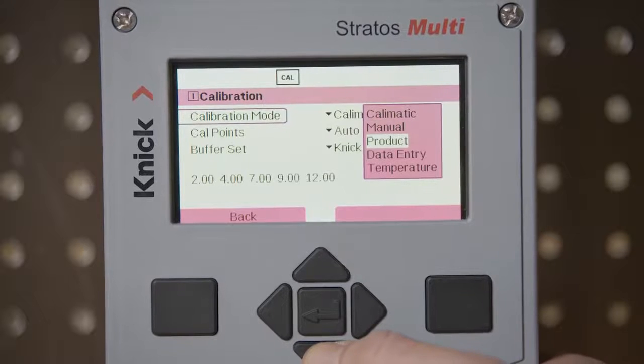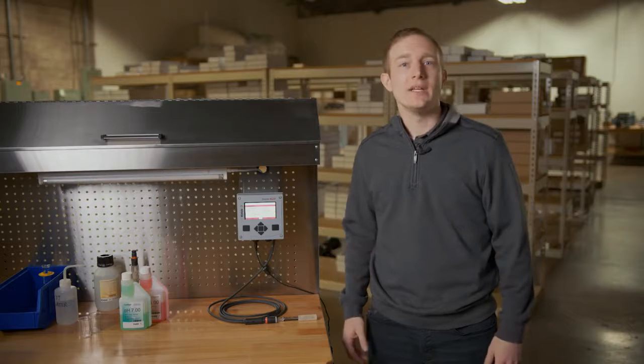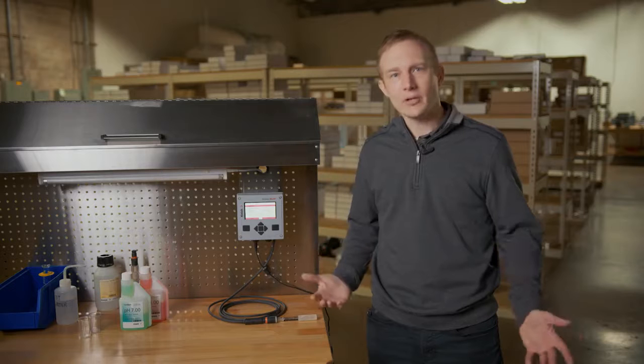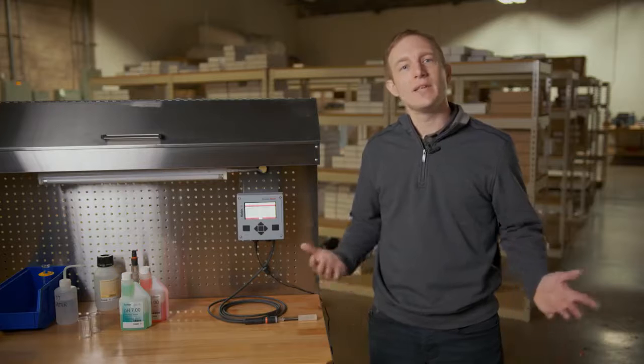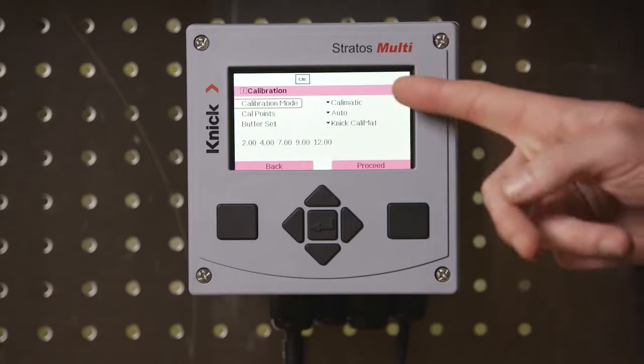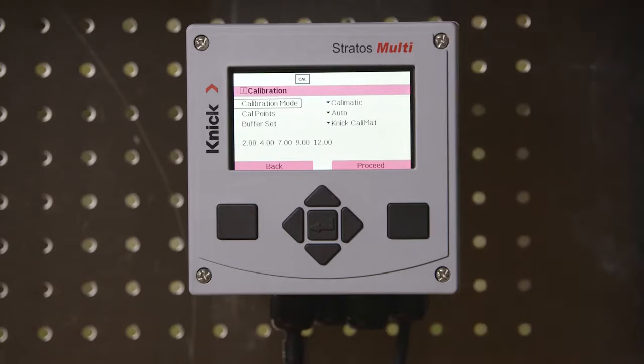when performing a calibration. The Stratos Multi also allows us to perform a manual calibration, a product calibration or single point standardization, adjustment of the electrode slope and 0 point via data entry, and lastly, an adjustment of the internal temperature detector. We will ensure that Calimatic is selected here before proceeding further.